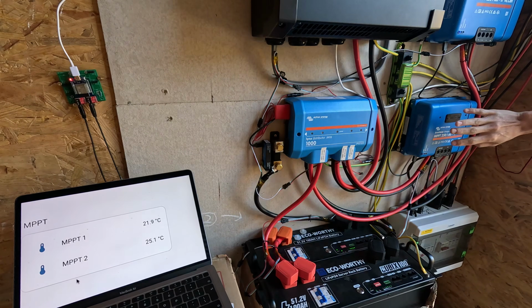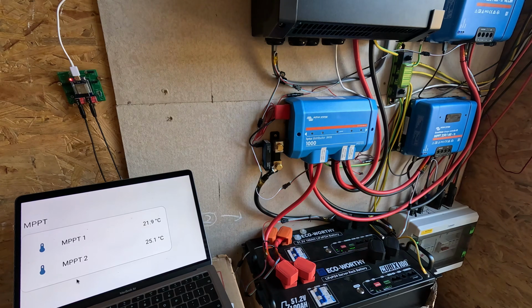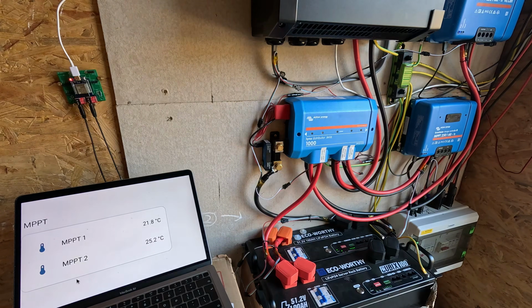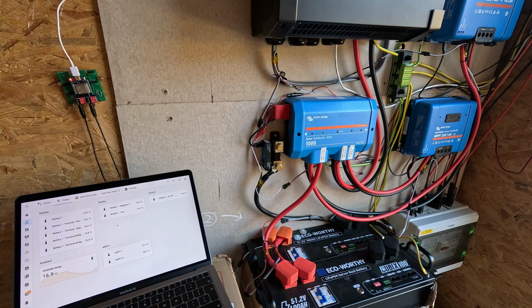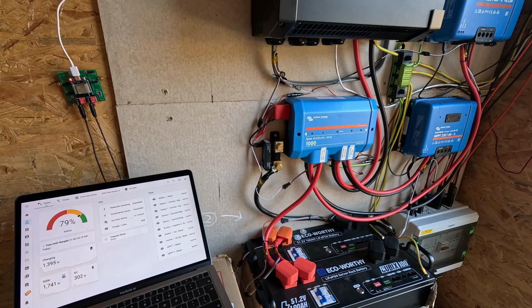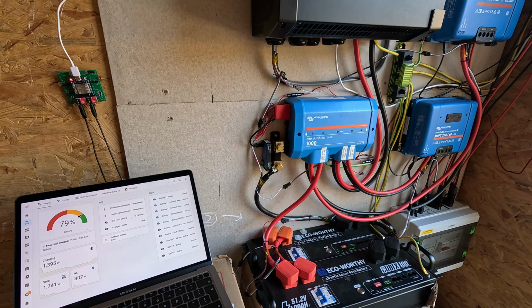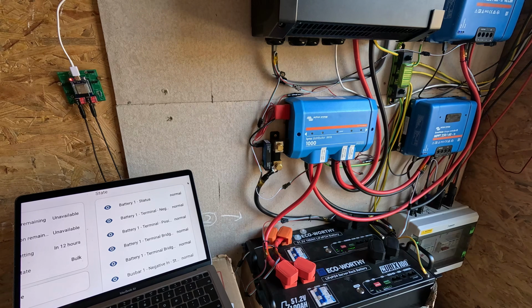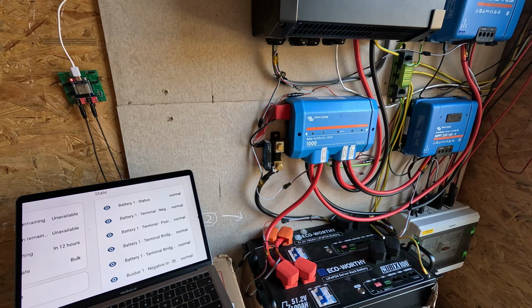If these ever hit 80 or 90 degrees, there would definitely be a problem, and I'd want to look at it anyway. Having the data available is good, but we also want defined states, so I've set the warning temperature at 35 degrees and the error temperature at 40 degrees. I'll probably tune that depending on how summer goes, if we're getting 37, 38 degrees anyway. Right now all the states are normal.